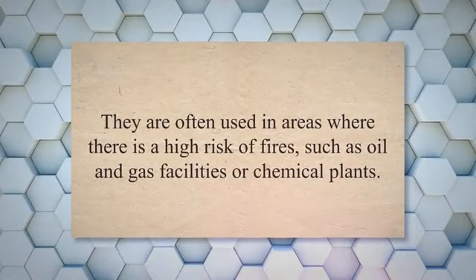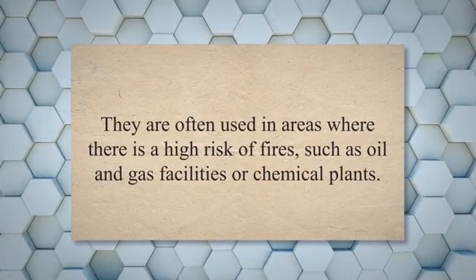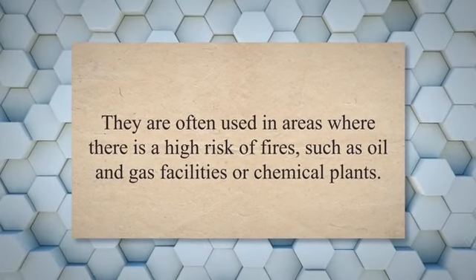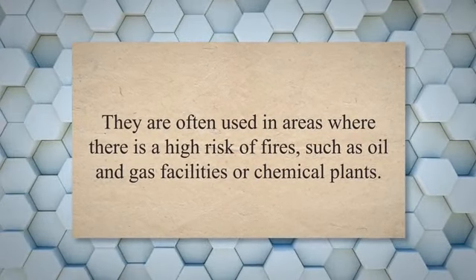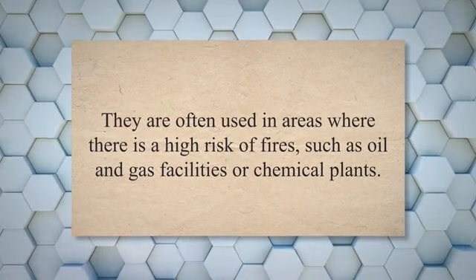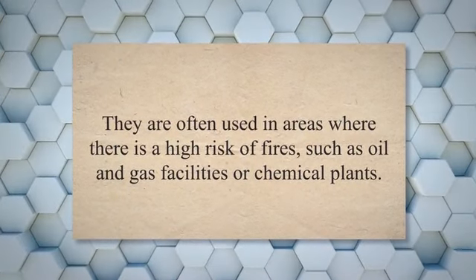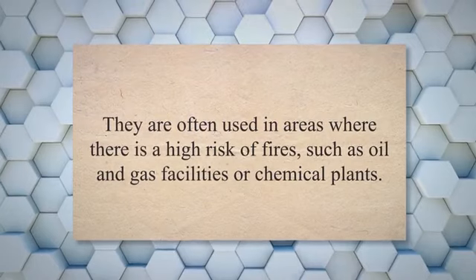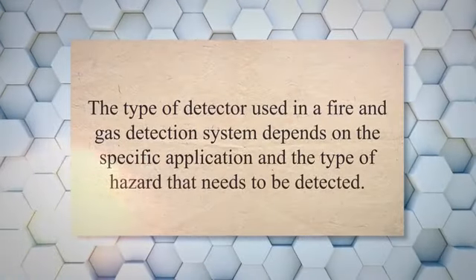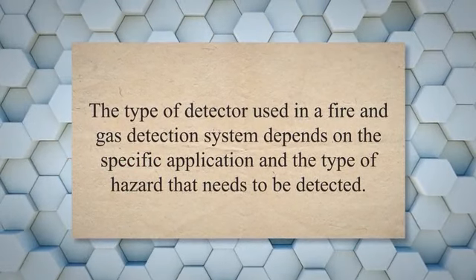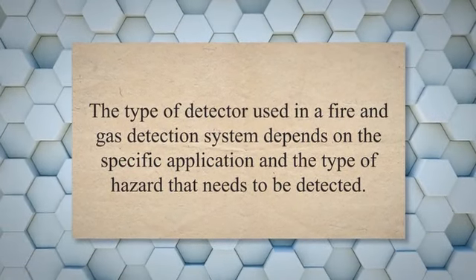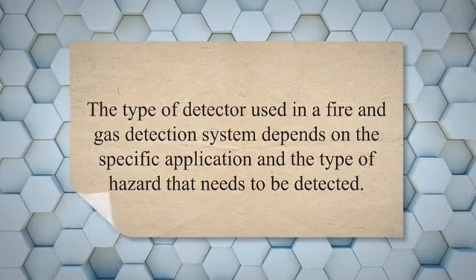Ultraviolet/infrared detectors. These detect invisible flames by sensing the ultraviolet and infrared radiation produced by flames. They are often used in areas where there is a high risk of fires, such as oil and gas facilities or chemical plants. The type of detector used in a fire and gas detection system depends on the specific application and the type of hazard that needs to be detected.